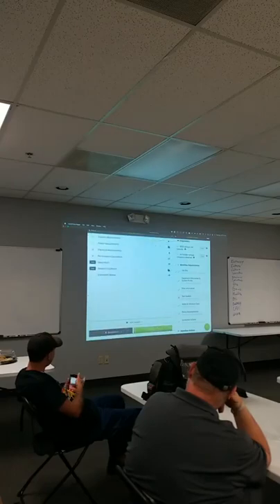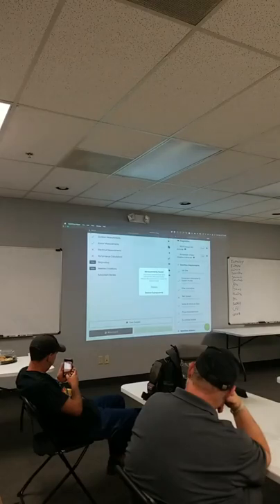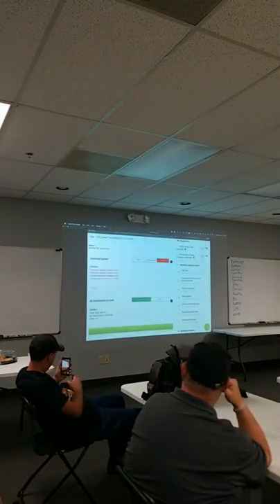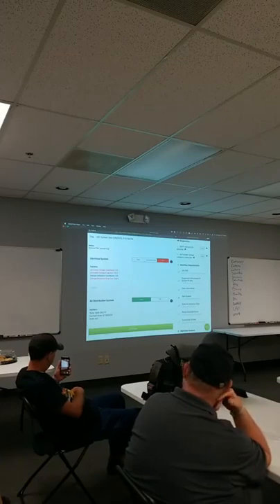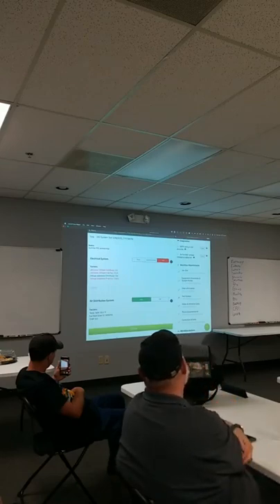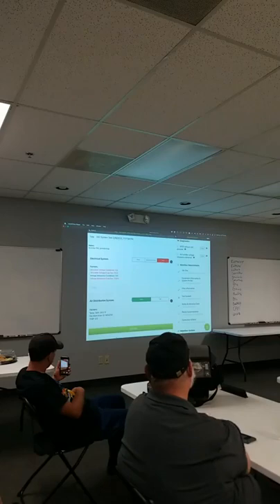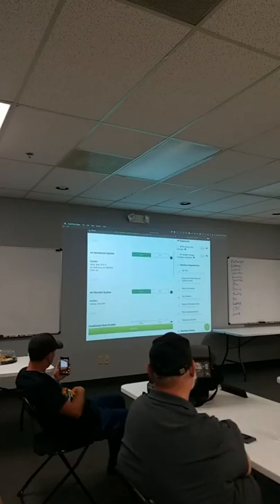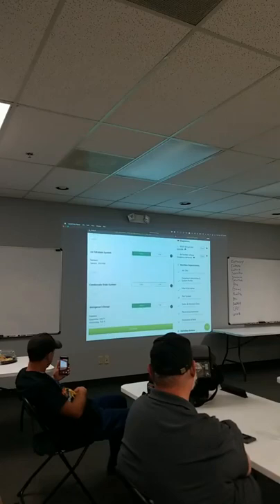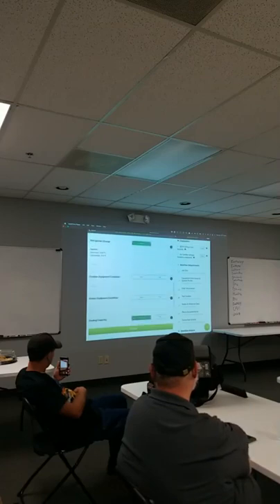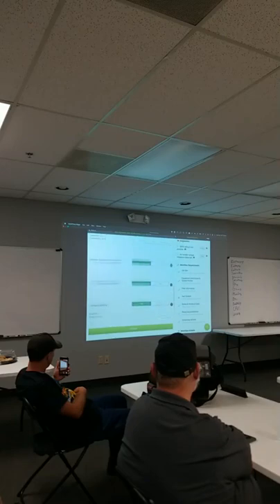We go to test the system. I'm just going to save a test out here and review the subsystems. It's automatically going to do the pass-fail. In this case my electrical system failed because my utilization voltages are out of range, and I have a voltage imbalance on my system. It detects the amount of voltage imbalance, in this case 15%, which would be pretty significant. It does your air distribution system, so it's looking at the temperature split, the fan watt draw, the total external static pressure, and how fast your air is going to cross your filters. Some of these you'd have to do yourself, so if you're doing a condensate drain, you'd pass-fail that. The charge, the superheat and subcooling are in range. You'd do your outdoor and indoor equipment condition. You can also add any notes you want to take.